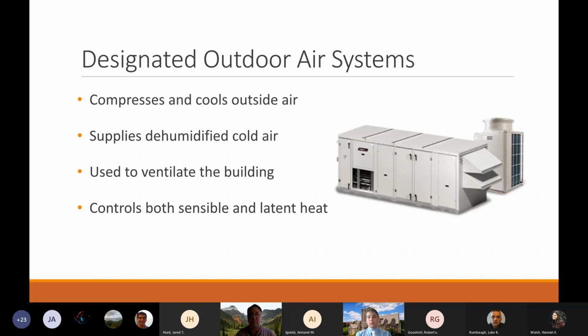We also went with 2 designated outdoor air systems, one of which is in the auditorium. We knew that there was some room to put ductwork in, as well as another designated outdoor air system for some of the rooms on the other side of the building where we knew there was room with drop ceilings as well. What a designated outdoor air system does, it's like your typical HVAC system. It compresses and cools the air outside and then feeds it through ductwork into the building. It supplies dehumidified cold air to cool off the building and keep the building from being humid. It's used to ventilate the building on the office side of the building where we don't need it to cool as well. So it controls both the sensible and latent heats. This is used obviously since we have the VRF system in the office buildings. It doesn't need to cool as well.